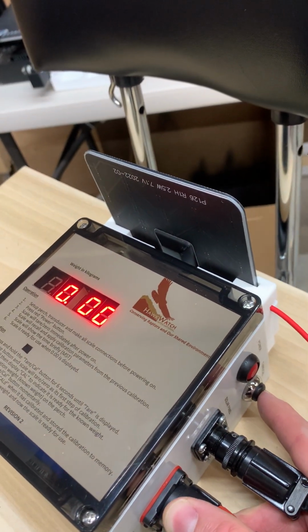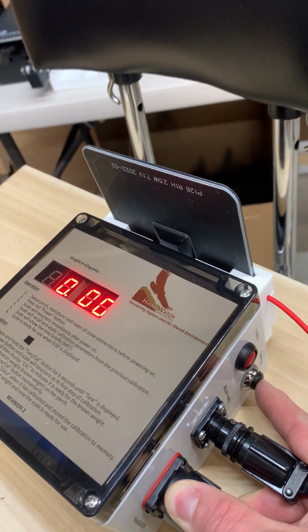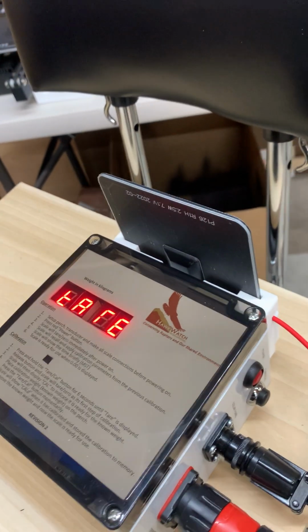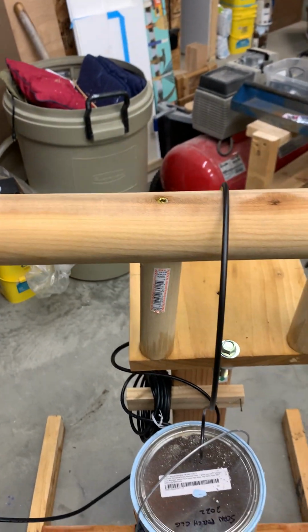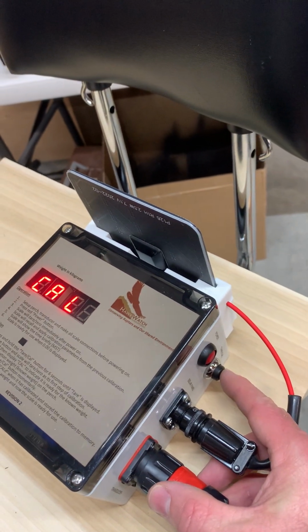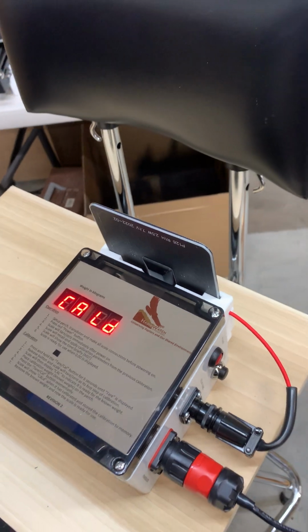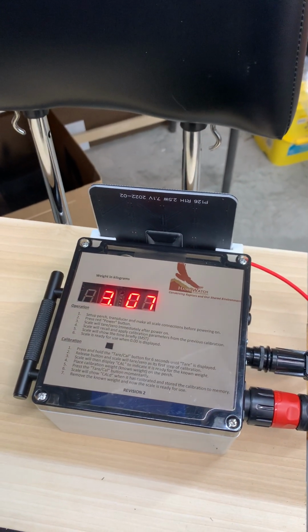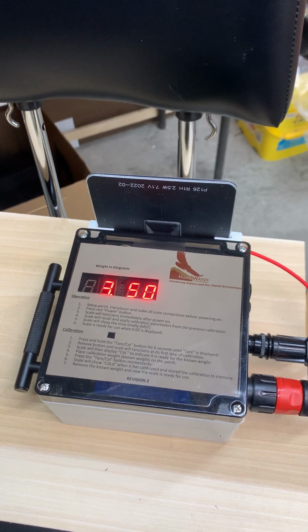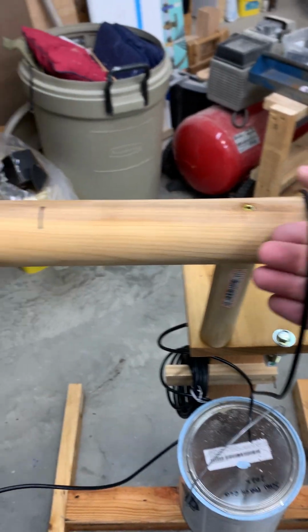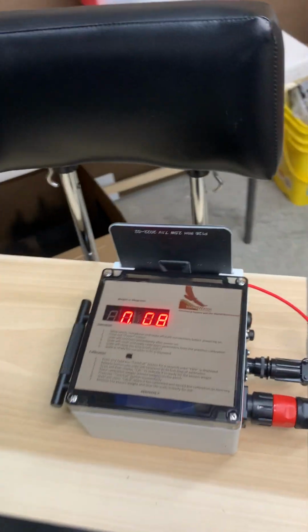Calibration is the same as before. You're just going to push and hold the cal button for 5 seconds. It'll display tare when it gets there. So there's tare. Just wait for it to tare. Then it says cal. It's waiting for the weight. So you hang your 3.5 kilogram weight on the perch. And then you're going to come over and hit the cal tare button again. And it'll say caled to tell you that it's calibrated. And then you can wait for it to show the weight. Should be 3.5 kilograms. And then you can remove your known weight, and now the scale is ready for use.